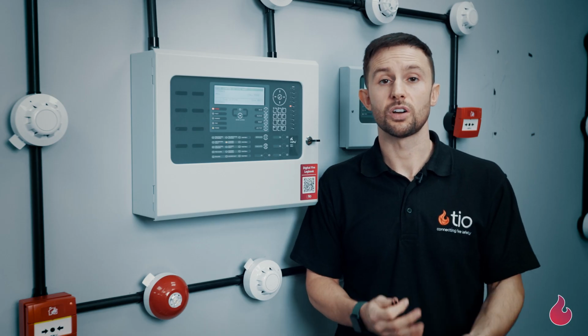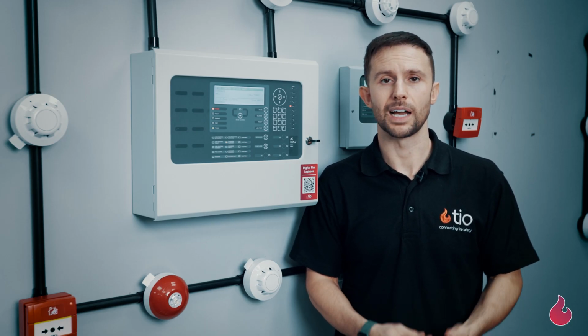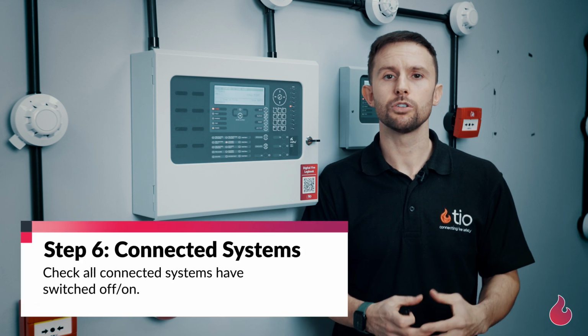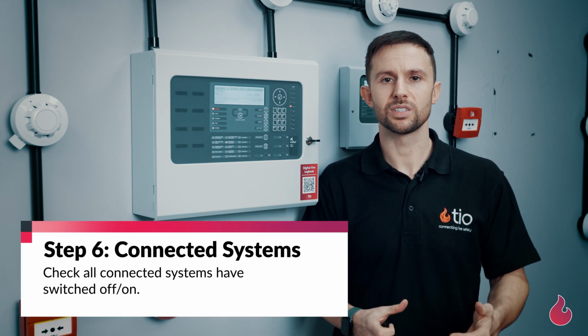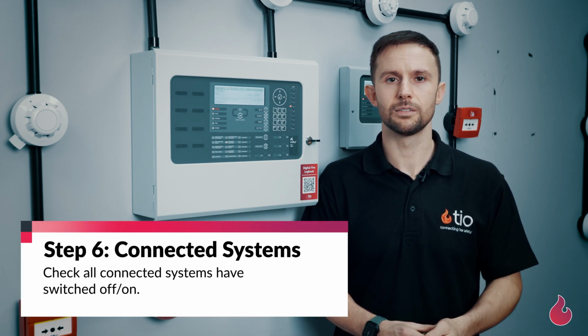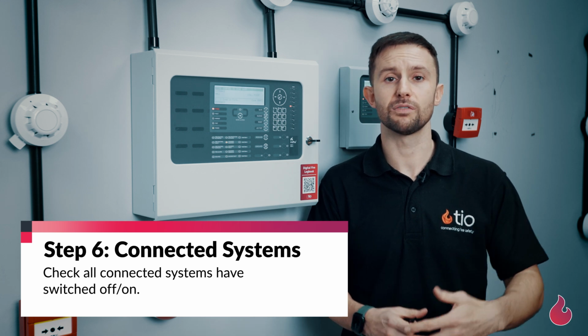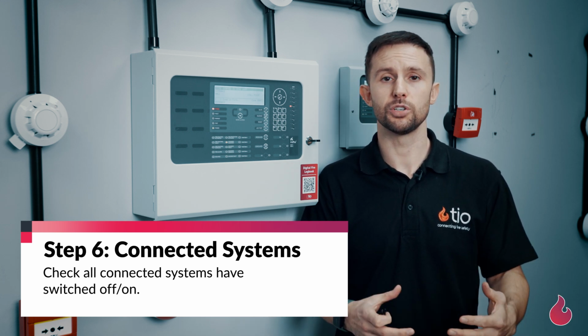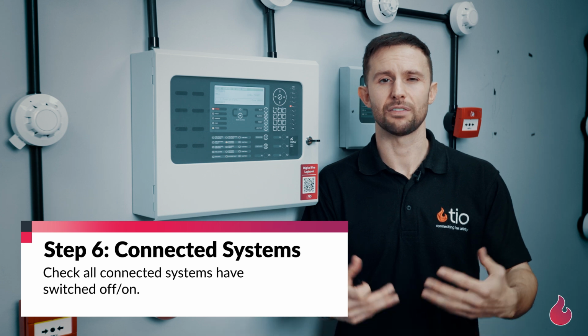Once you've successfully silenced the sounders in the building and you've muted the fire alarm panel, you can now go check your connected systems. For example, if your air conditioning is connected, or your lifts, or for example, if it activates another building, this is the time to go and check that those connected systems have successfully activated.